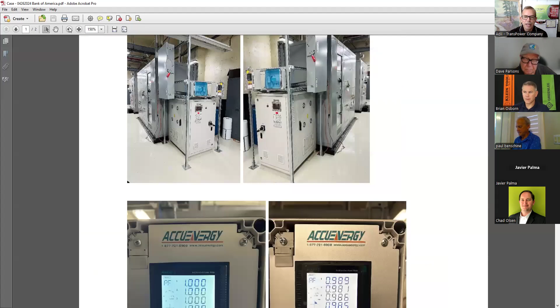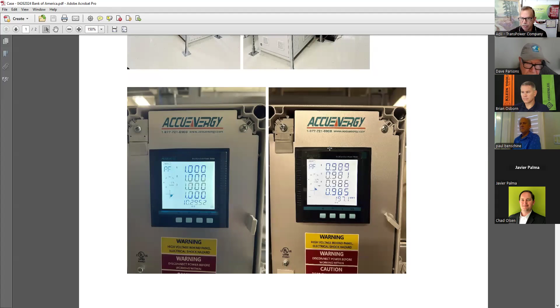And then when you turn it on at 1 o'clock in the afternoon, this is what you saw. The power factor on both switch gears - on one side it's showing 1.00, the other is showing 0.98.